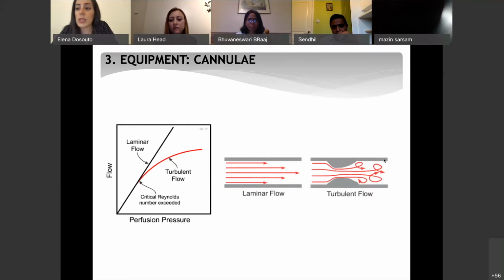And then we select a cannula depending on how much flow we need to deliver to this patient. Ideally, we like to see what we call laminar flow. So as you can see, all is straight in line, really nice, within the ECMO cannulas and the surrogate. This is because when the pressure in the cannula is too high, you can see the pressure rising in here, there will be a point where the flow changes from laminar to turbulent, which is highlighted here on the right.